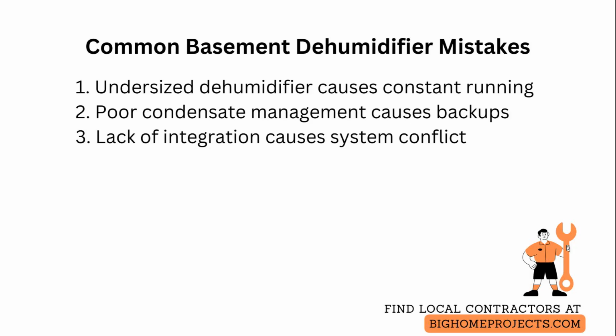Always provide a dedicated drain, trap primer, or a properly rated pump, and test the discharge at startup. Third, lack of integration with the ventilation or thermostat can cause cycles that fight the air system. Wire the dehumidifier to the HVAC control or set a coordinated control strategy so the systems complement each other.